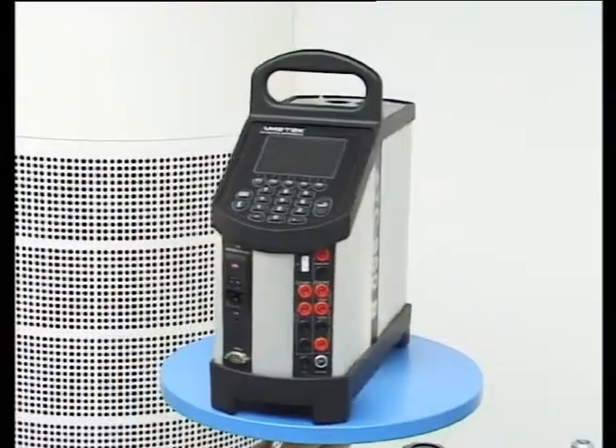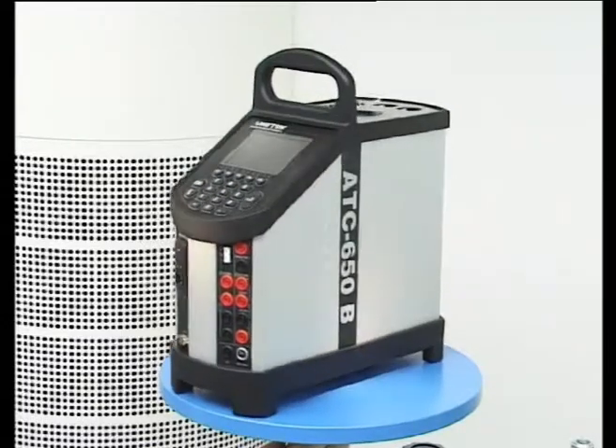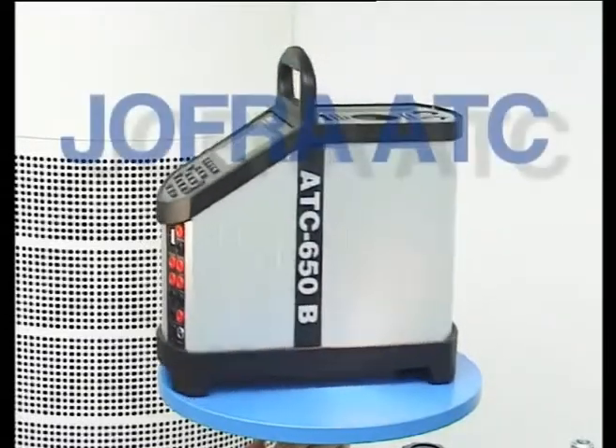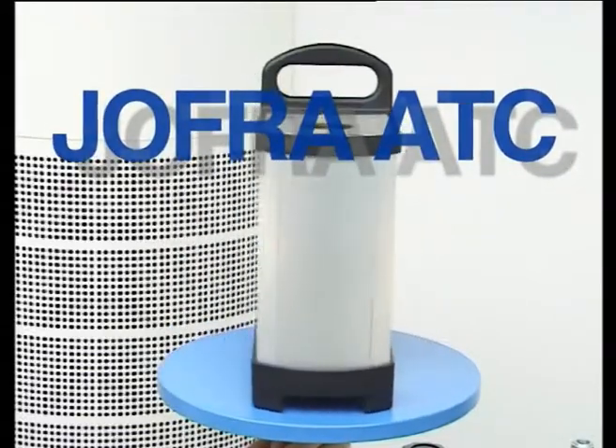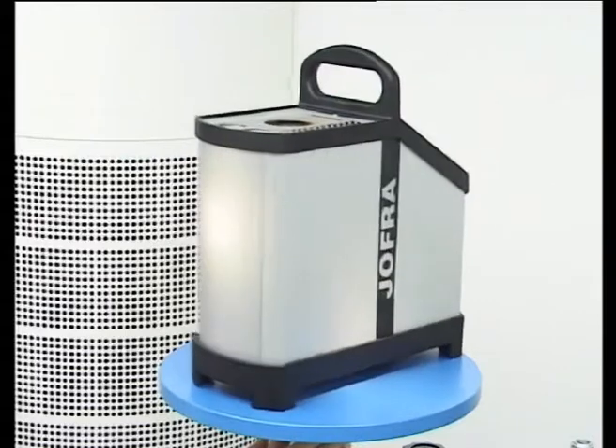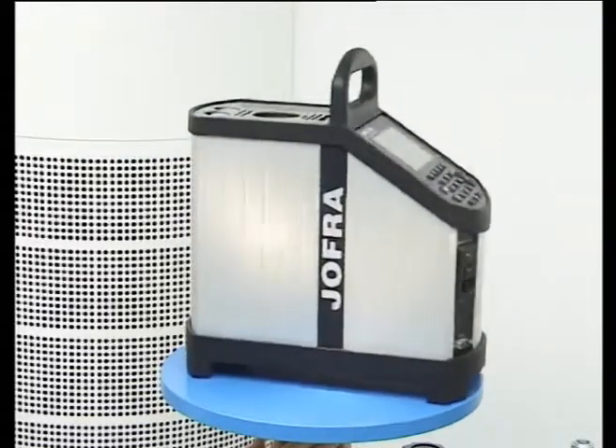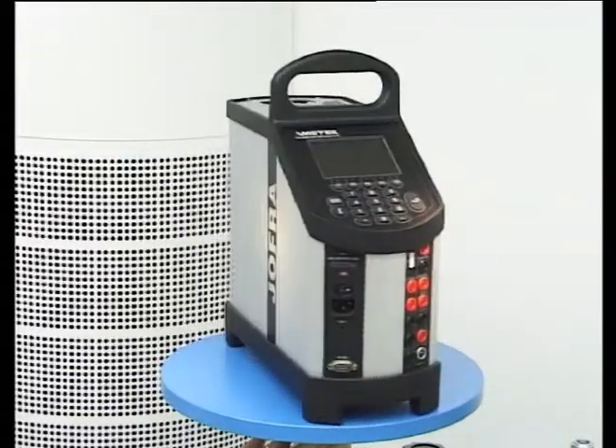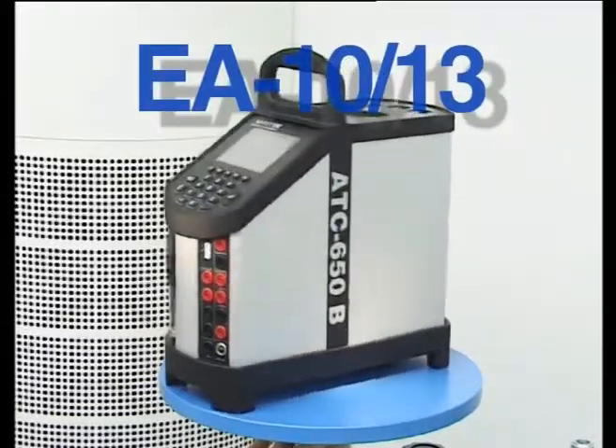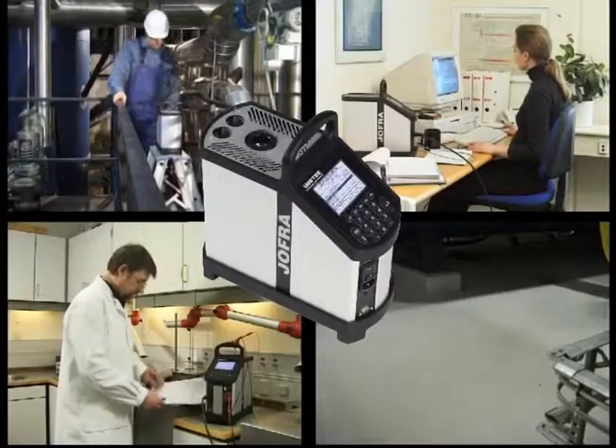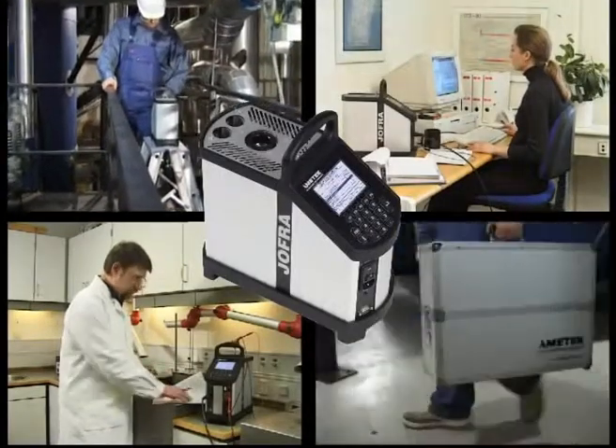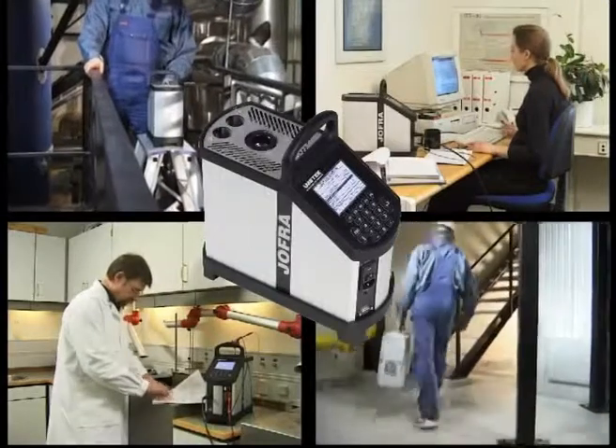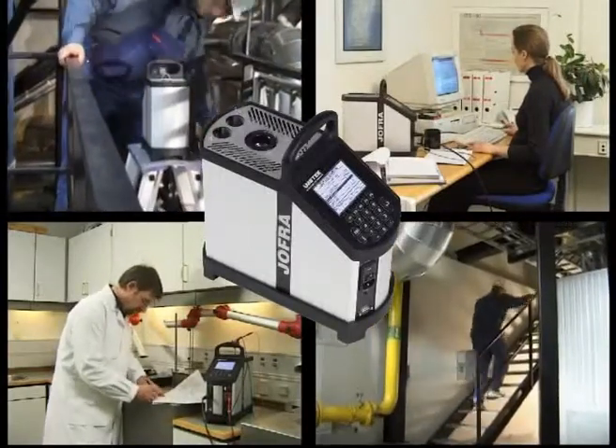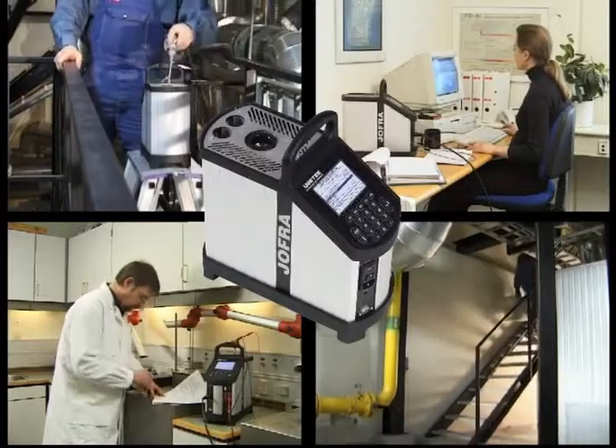Now, entering the new millennium, Ametek is ready to introduce a product that will set new standards for industrial temperature calibration. The Advanced Temperature Calibrator, called the JOFRA ATC series. With its completely new core element, this series is designed to meet the new EA guidelines established by European standard laboratories. The JOFRA ATC series combines the accuracy of laboratory calibrators with the speed and portability of dry block calibrators. Ametek is taking dry block calibrators into a new dimension.